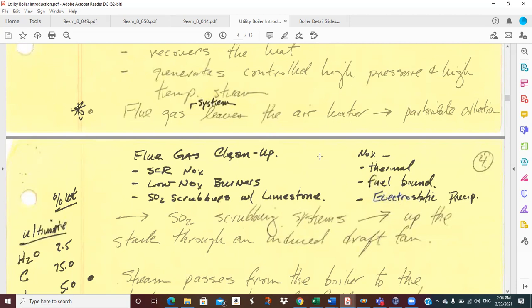Selective catalytic reduction is a main technology for NOx control. Burners you can purchase in newer units would have low NOx burners, could burn natural gas. And we'll talk a little bit about some of that technology.